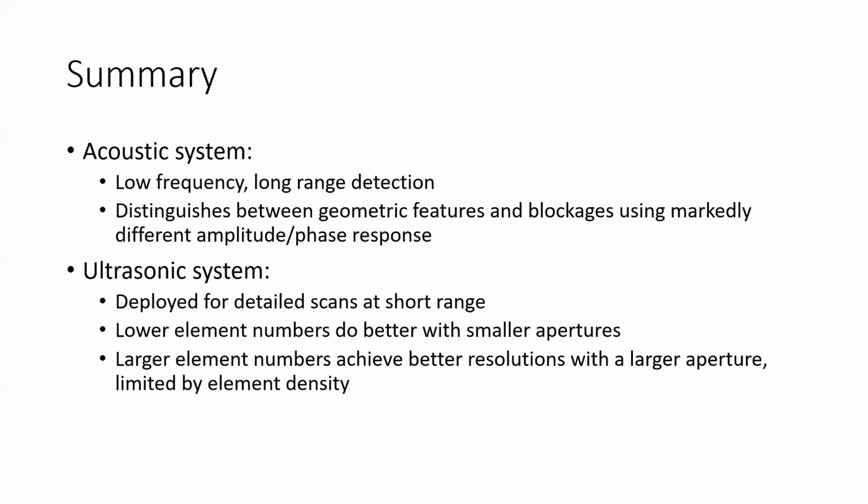And if you're using a lower number of elements there, it makes sense to reduce it to a tighter aperture so you have that element density to get decent images. But if you have enough elements to have a wide aperture, you can ultimately reach better performance with this.